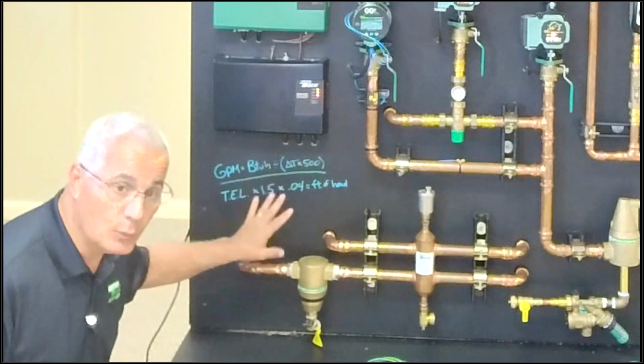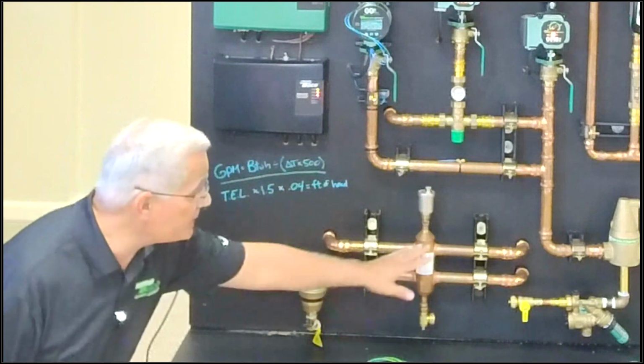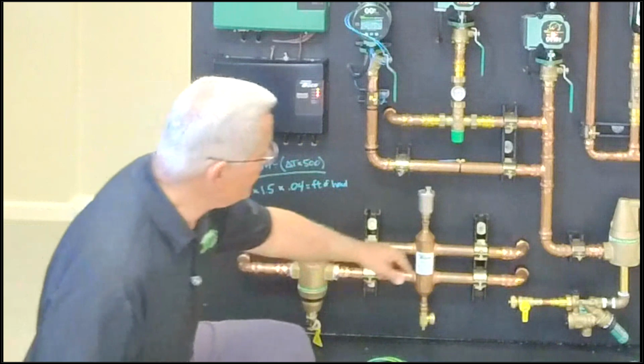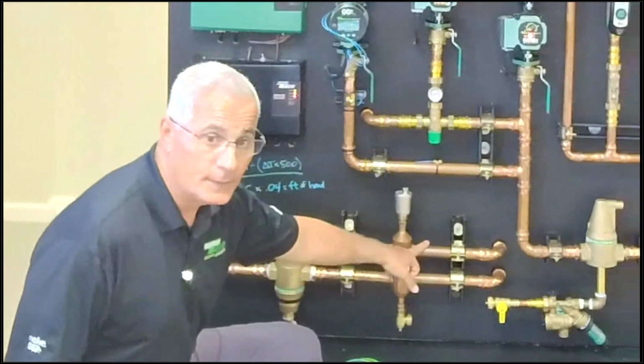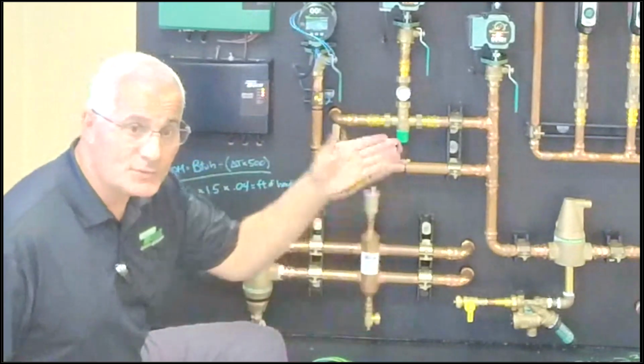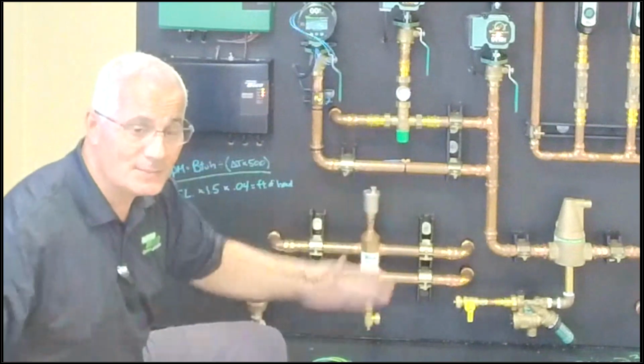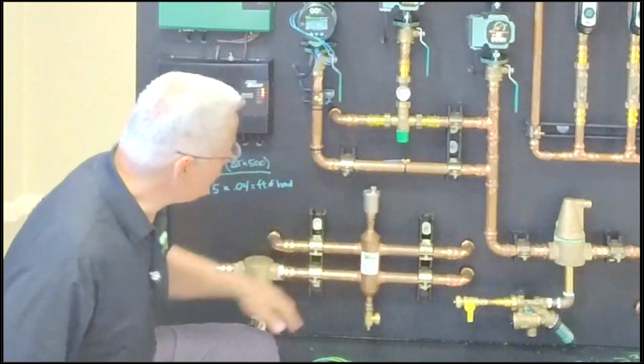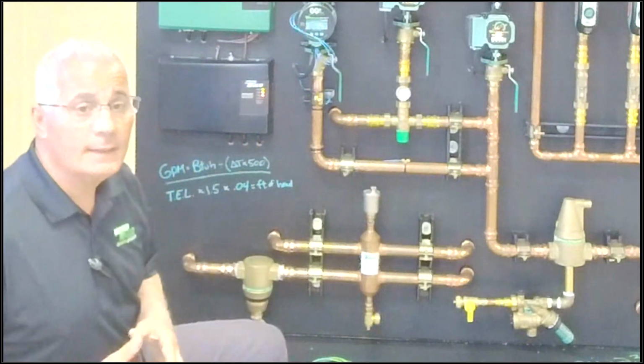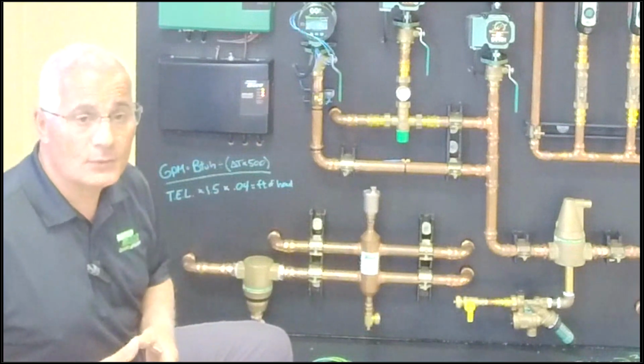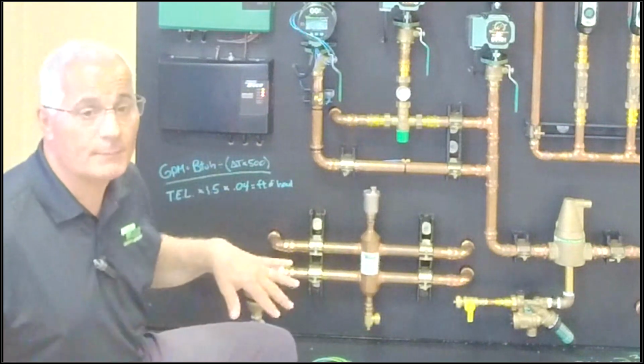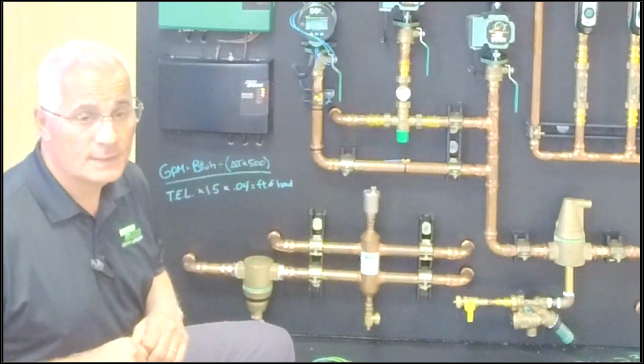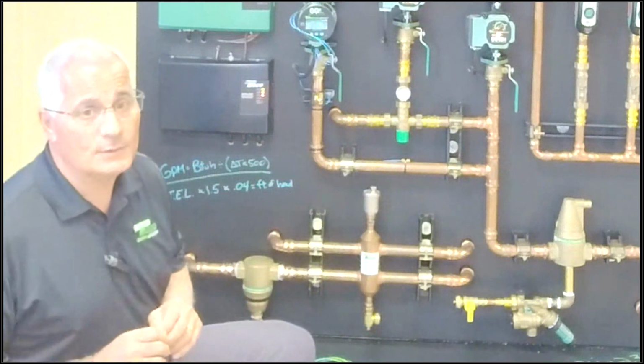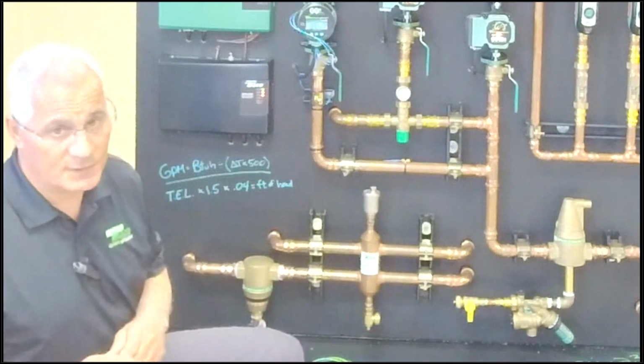So the boiler circulator is not going to see my system circulator, which would be on this side here. I've got flow rate on the boiler side here. I've got flow rate on the system side here. Yeah, there's some mixing, but that's not the primary use of this low loss header. It's to hydraulically separate the two systems. And this is something you need to do when you do anybody's condensing boiler.